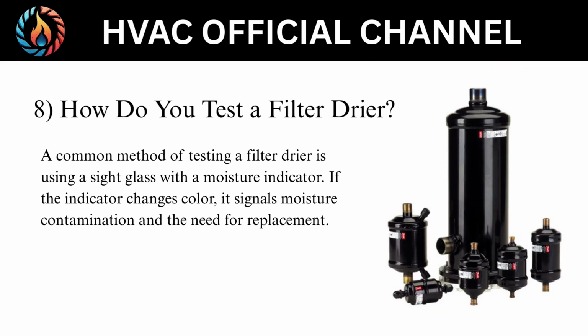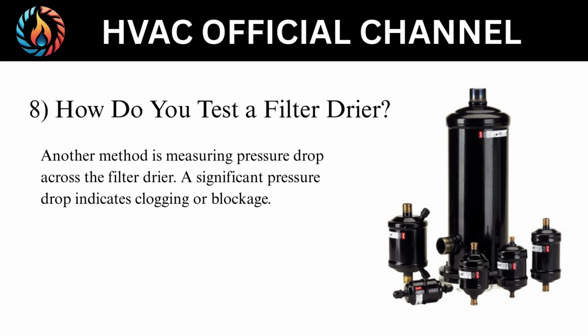8. How do you test a filter dryer? A common method of testing a filter dryer is using a sight glass with a moisture indicator. If the indicator changes color, it signals moisture contamination and the need for replacement. Another method is measuring pressure drop across the filter dryer. A significant pressure drop indicates clogging or blockage.